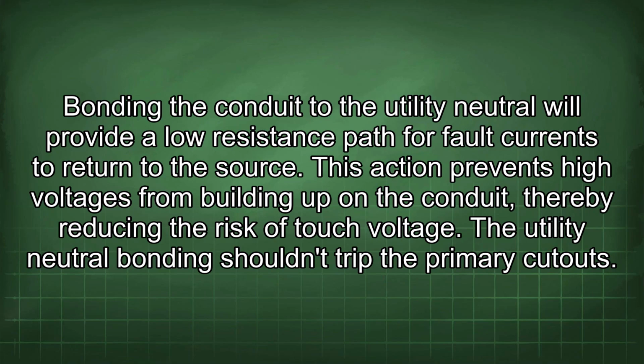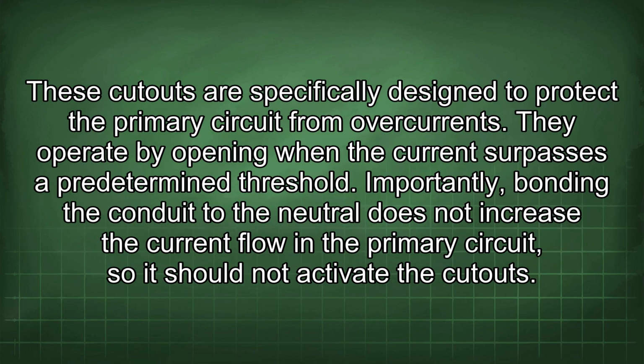Bonding the conduit to the utility neutral will provide a low-resistance path for fault currents to return to the source. This action prevents high voltages from building up in the conduit, thereby reducing the risk of touch voltage. The utility neutral bonding shouldn't trip the primary cutouts. These cutouts are specifically designed to protect the primary circuit from overcurrents.